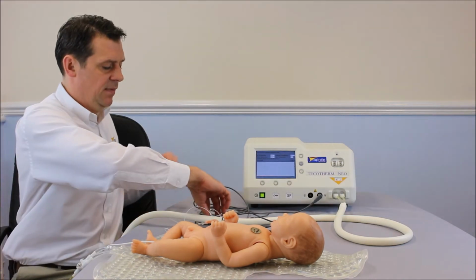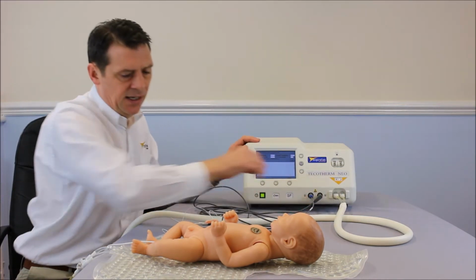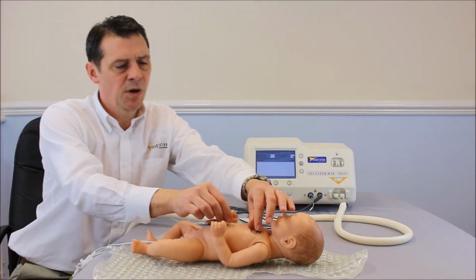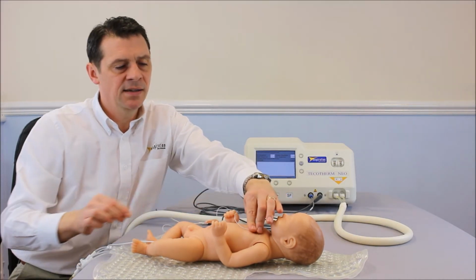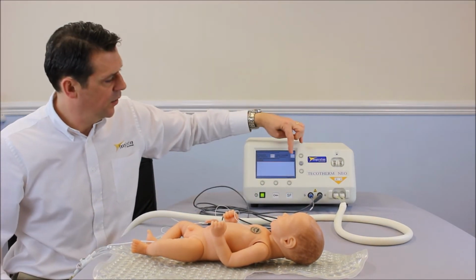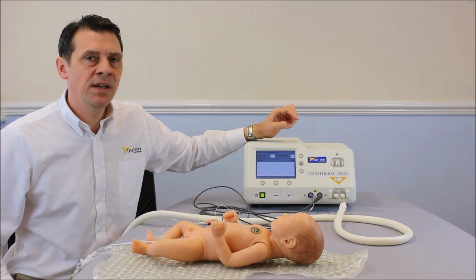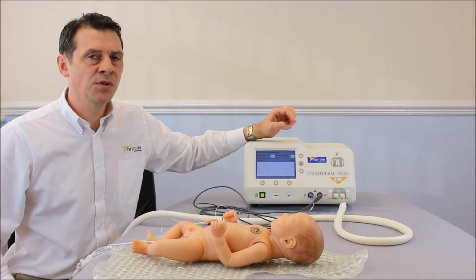You can also connect an optional skin temperature probe for monitoring only. We connect up to the S side here, disposable probe either to the chest or the forehead, and that will be displayed on the bottom right value here. Remember, it is only for reference only, it's not servo controlled.